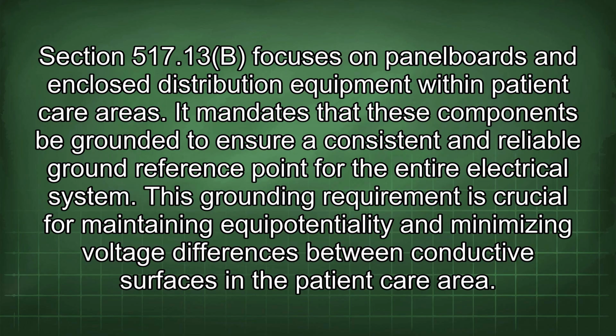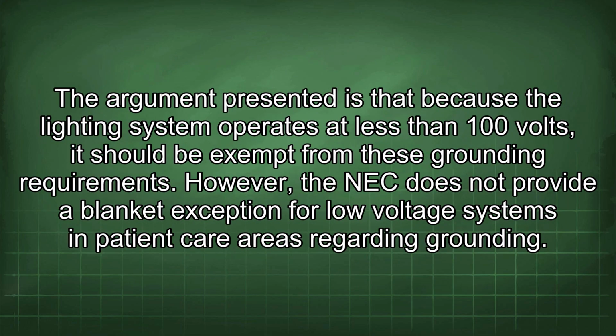Section 517.13(B) focuses on panelboards and enclosed distribution equipment within patient care areas. It mandates that these components be grounded to ensure a consistent and reliable ground reference point for the entire electrical system. This grounding requirement is crucial for maintaining equipotentiality and minimizing voltage differences between conductive surfaces in the patient care area.